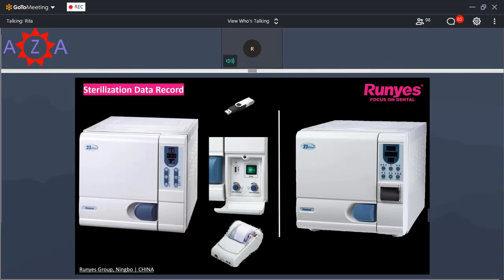Now let's talk about the data records. According to the requirements of the MOH for sterilization records, the clinic needs to keep sterilization records of the instruments every day. For the convenience of clinic operations, we have two different methods of data storage. One is printer, another one is USB. You can choose one of them according to the local situation. If the local MOH doesn't specify the format of the sterilization records, we recommend the USB because the PCB of the autoclave can hold up to 2,000 cycles. So the clinics don't need to download the records every time. They can do it according to the clinic situation.